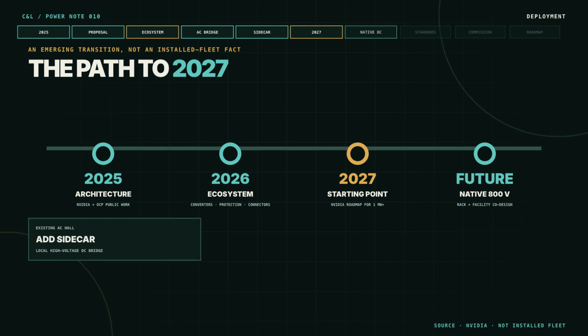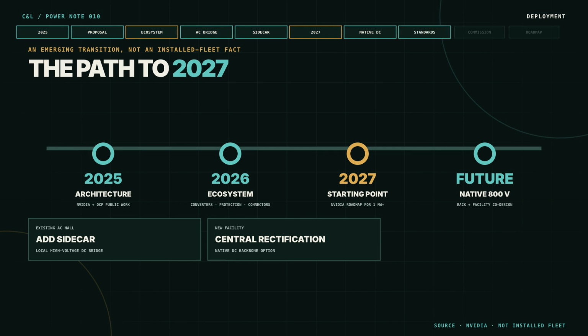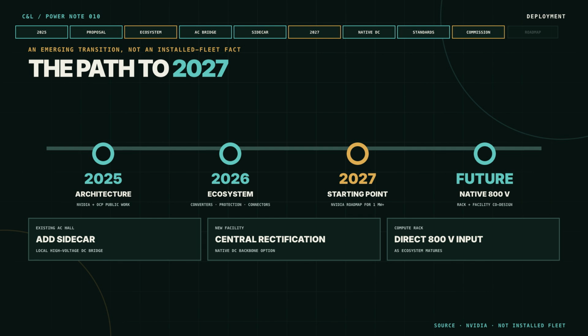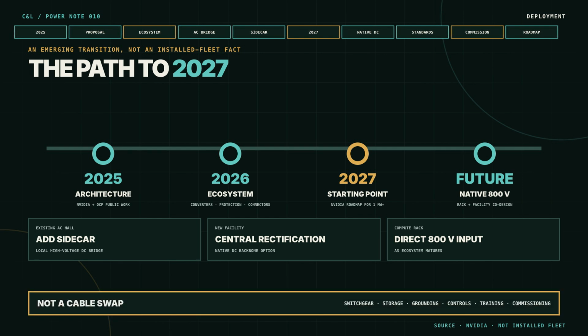Each step changes procurement and commissioning. Switchgear, battery strategy, grounding, controls, spare parts, training, and emergency procedures move with the voltage. A retrofit is not a cable swap. The economic case should compare specific old and new one-line diagrams at the same capacity, redundancy, load curve, and service level. Anything broader is marketing before engineering.